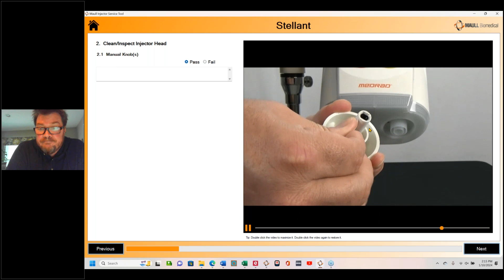So I'm going to get into the cleaning and so forth of the injector head. So very first step here, manual knobs, and the video is showing how to remove the manual knobs, clean them, and so forth. So I'll click, we'll say pass. Then it's also going to go into a little metal strain relief inside the manual knobs to make sure that that piece of metal's there. It's talking about cracking around the manual knob and, if it's minor cracking, as the audio would say, just use tape to secure it. If it's major cracking, then you would have to go ahead and replace the entire manual knob. And well done.